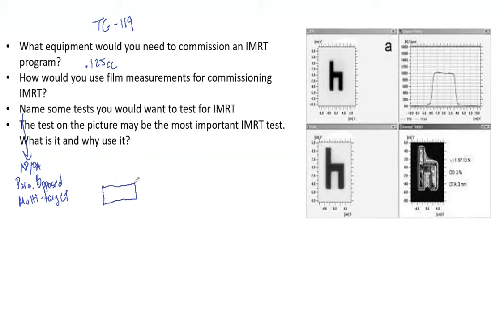One thing I would certainly consider is a band plan: say two gray here, 1.5 gray here, and one gray here along the film length. As the MLCs move, you can see they trail and give more dose in one region, are partially covered in the next, and even more modulated in the third. You can analyze that band very easily and really test how good your MLCs are.